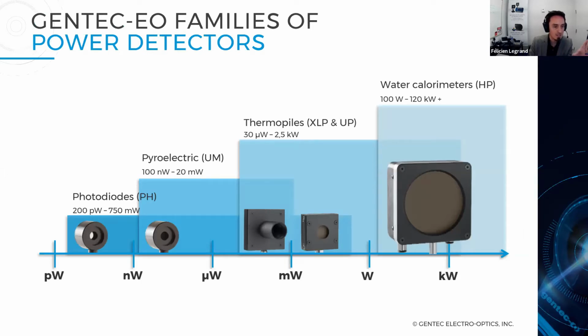Presentation here. What kind of technology is typically available to measure laser power? From the picowatt level, we mainly use photodiodes, really sensitive photodiodes, also providing NIST traceable measurement. Then going from the milliwatt to the hundreds of watts, and up to the 2.5 kilowatt range, we use thermopile detectors. And then above, in the kilowatt range up to hundreds of kilowatts, we use water calorimeters, where they measure a difference in temperature between the inlet and outlet, and the water flow rate is used to derive the incoming laser power.